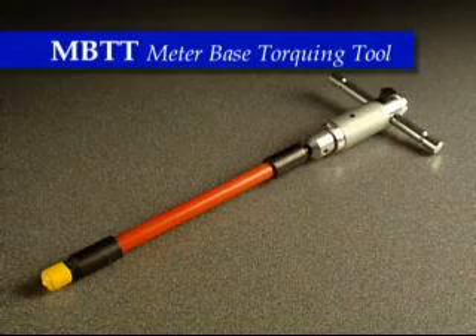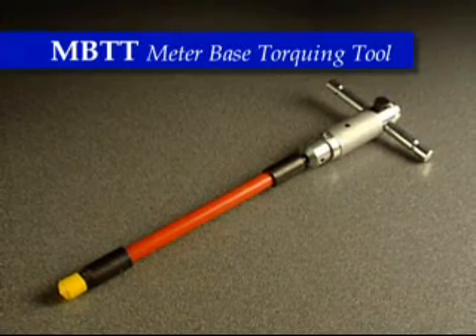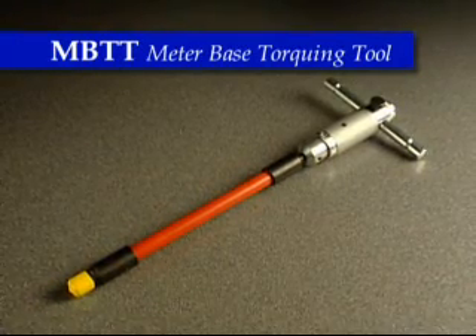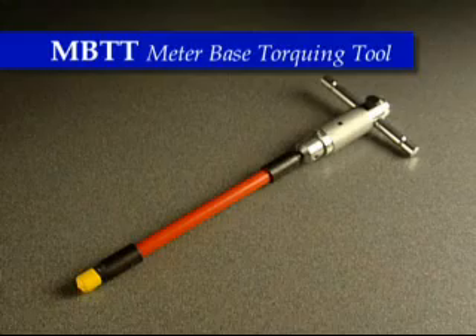The MBTT 150 meter base torquing tool allows the proper insertion of Landis+Gyr K-base, three phase or similar meters without shorting, sparking, or causing flashover. The MBTT socket end is isolated from the tool's handle by an insulated composite shaft which is rated to a thousand volts.